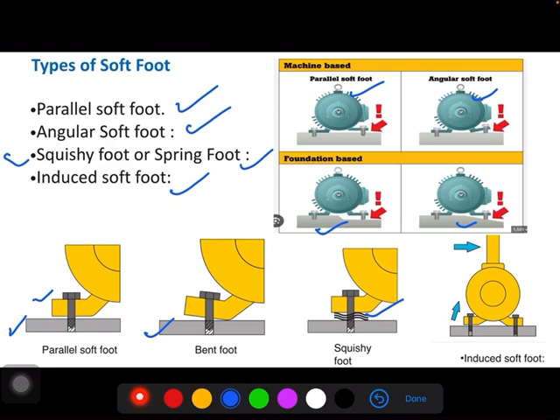Last one is induced soft foot. What is induced soft foot? It is because of external forces. When you connect the suction and delivery pipe for the pump and they are in stress condition, then it creates the soft foot. Sometimes couplings are in stress, or in case of some equipment that are in overhang, that also creates the soft foot.